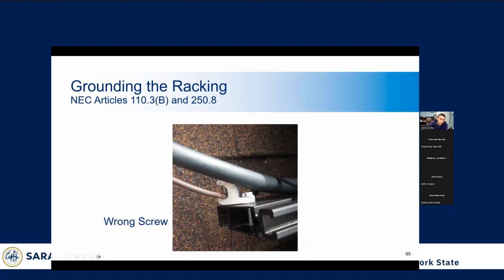In many applications, you'll see that contractors have bonded the rails themselves as a way to provide a path through the system. And they do that through a lay-in lug like the one pictured here. However, this lug was installed with a screw that's not rated for bonding purposes. So it's getting right into the nitty-gritty of the code. But typically for this, you'll need a finely threaded machine screw. You want to make sure that there's at least 2 threads on the metal of connection for this situation. That's to ensure that there's a proper amount of area to hold the current that could potentially be moving through here. So this one would not pass the inspection.